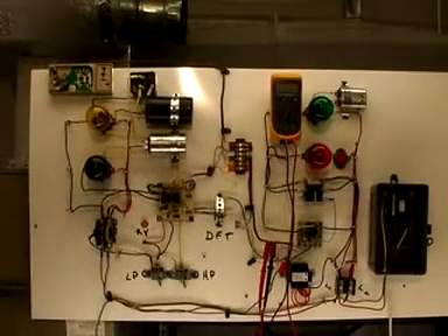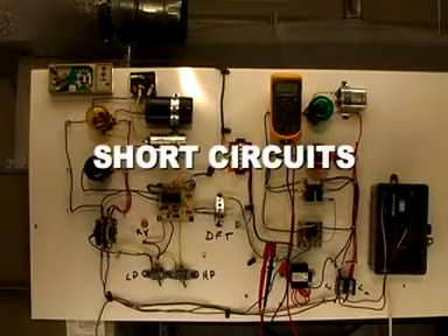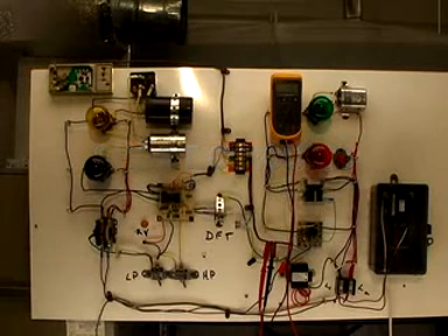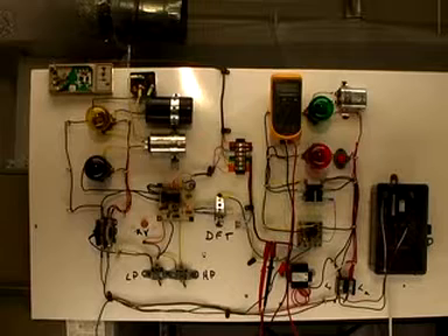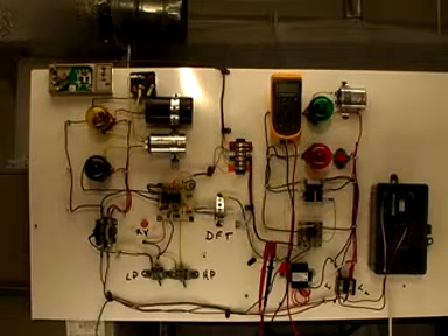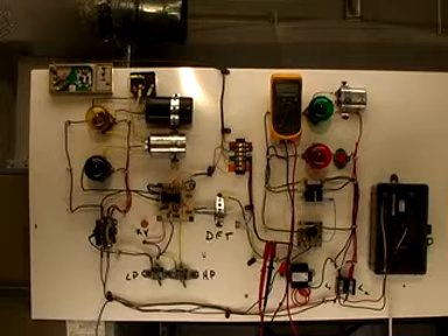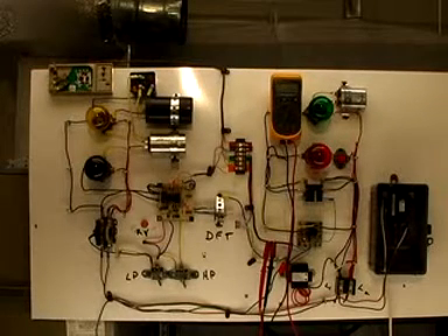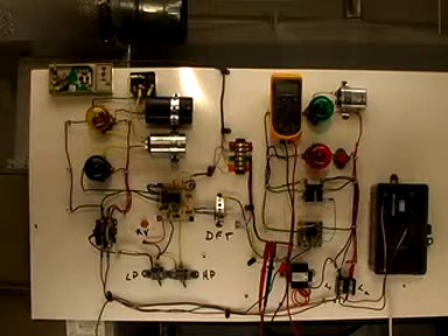The only two ways I know to find a short circuit is either use your multimeter on the ohm scale and run some resistance checks through the circuits. Either you can do it up at the thermostat, or you can do it at the air handler where you've got some connections to check. And then the other way, which usually turns out to be faster, is just replace everything, put a fuse in the circuit or in the system, and then just energize one circuit at a time.